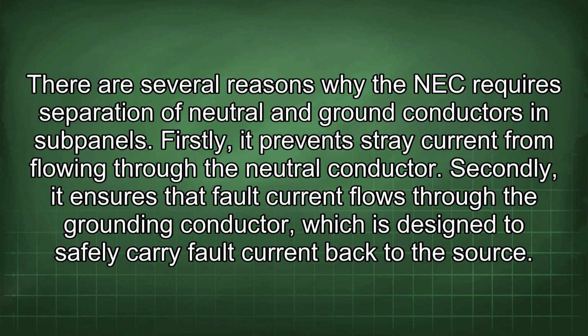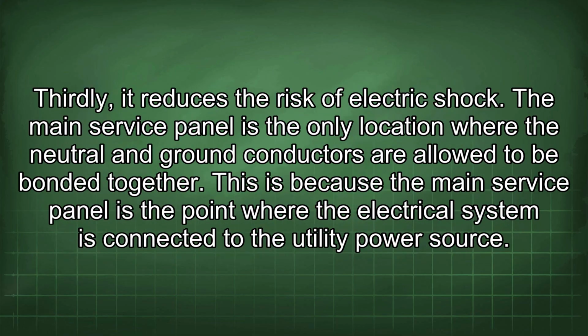There are several reasons why the NEC requires separation of neutral and ground conductors in subpanels. Firstly, it prevents stray current from flowing through the neutral conductor. Secondly, it ensures that fault current flows through the grounding conductor, which is designed to safely carry fault current back to the source. Thirdly, it reduces the risk of electric shock.